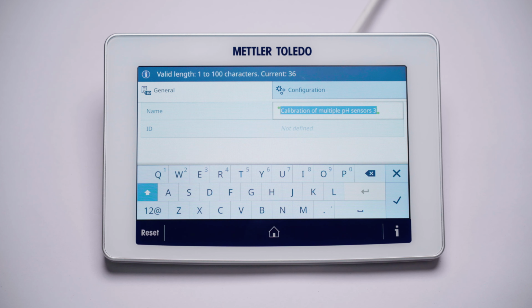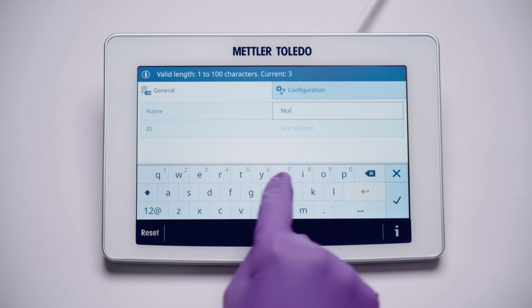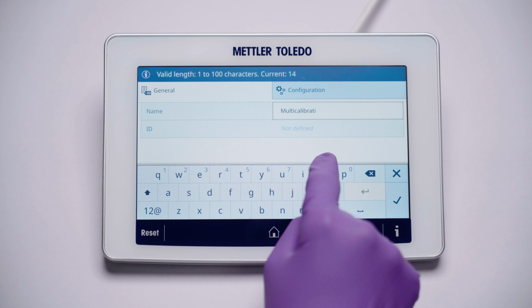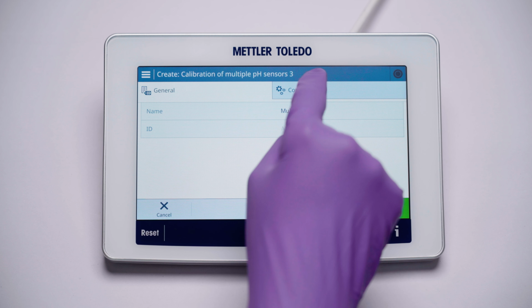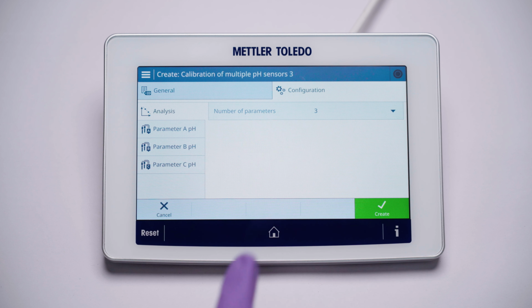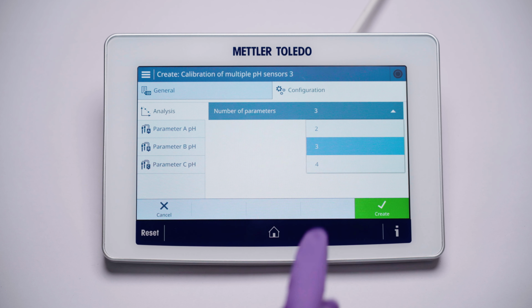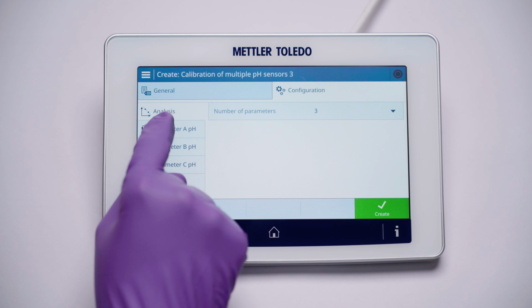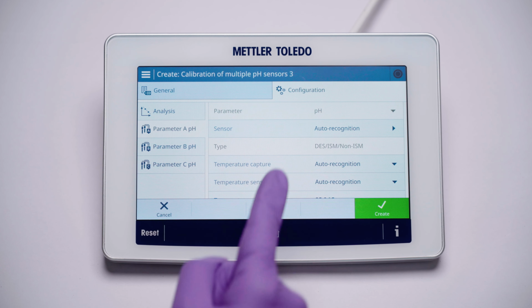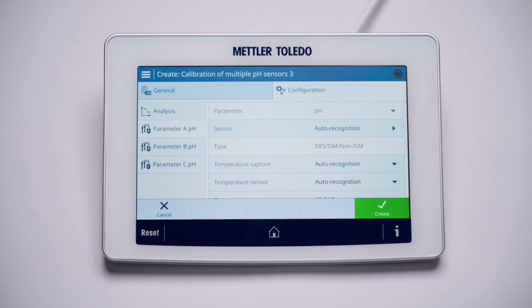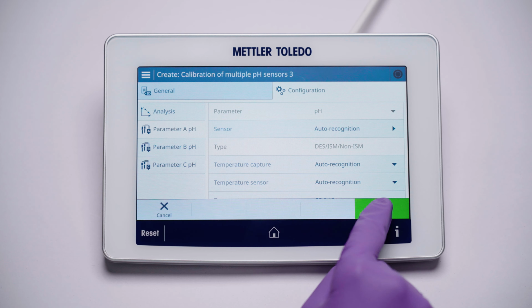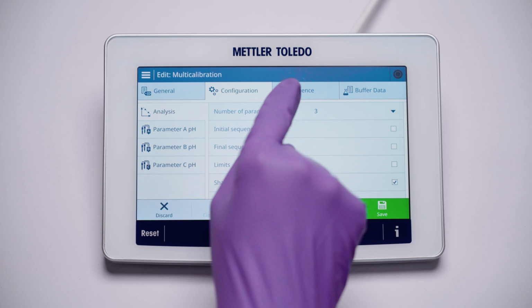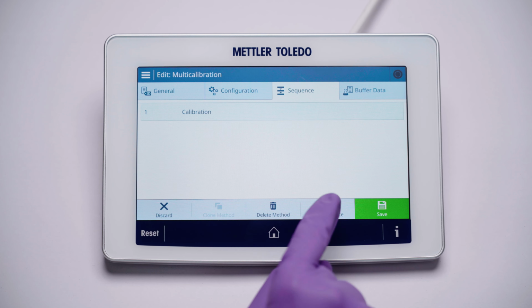Now we'll name our method Multicalibration. When we navigate to Configuration, we can select the number of parameters. In our case, we'll select 3. We'll choose parameter A. Here, you'll notice that the pH parameter cannot be modified. Multi-sensor calibration is only available for pH. Click Create.